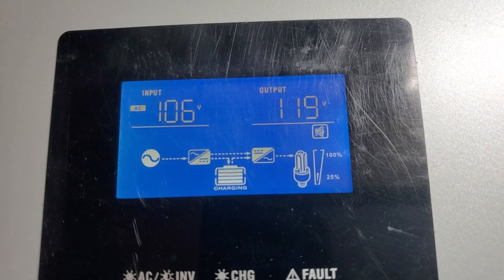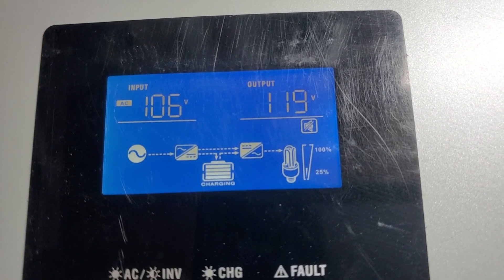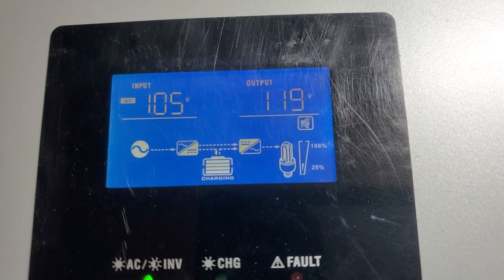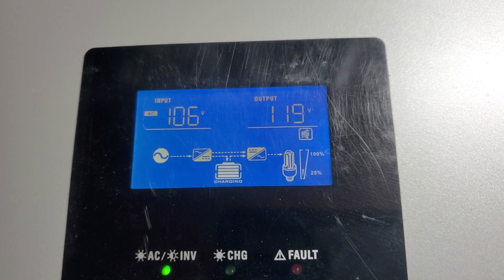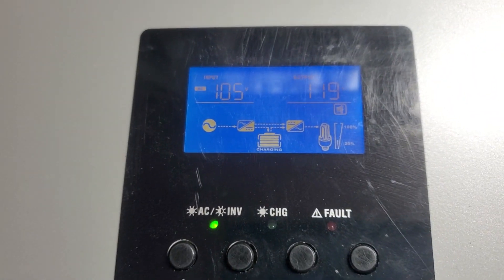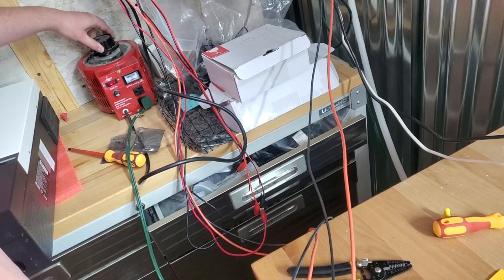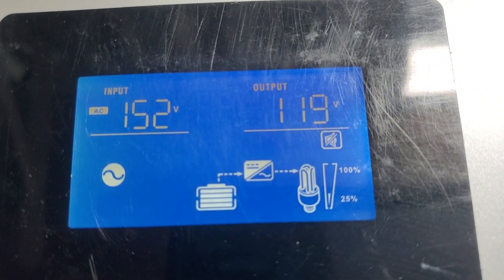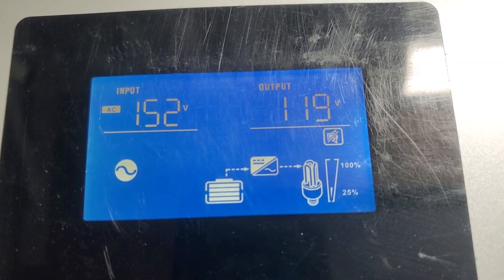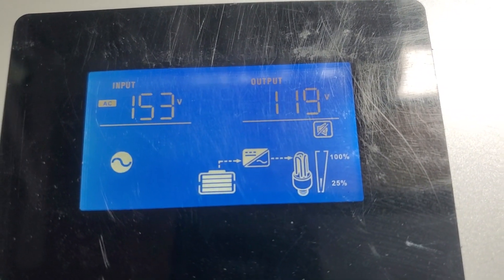See, 106V still giving out 120V. Now another special thing about this unit is you can even up the voltage all the way too. Up it as high as it'll go. All the way. Okay, 154V is obviously too much. It'll turn off, go down a bit, a little bit, until we hear it click.